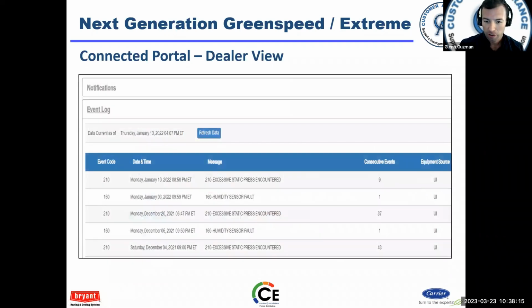There's also a plethora of information. Scroll down here, for example, you click on the event log and it'll bring up all the fault codes. So a customer calls in and says, hey, it says there's a fault on my thermostat. Well, I can log in and see, hey, excessive static, excessive static. So they got some air flow issues going on. Now I can send the tech out, make sure he's able to identify these airflow issues and get them resolved.